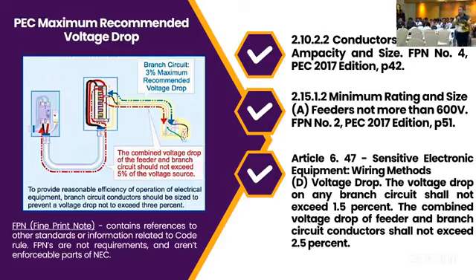Okay. So conductors, minimum ampacity and size, minimum ratings and size, feeders not more than 600. Then we have Article 6.47, Sensitive Electronic Equipment Wiring Methods. Sa Section D, voltage drop: the voltage drop of any branch circuit shall not exceed 1.5%, and the combined voltage drop of the feeder and branch circuit conductors shall not exceed 2.5%. This is intended for the sensitive electronic devices. Okay, next.